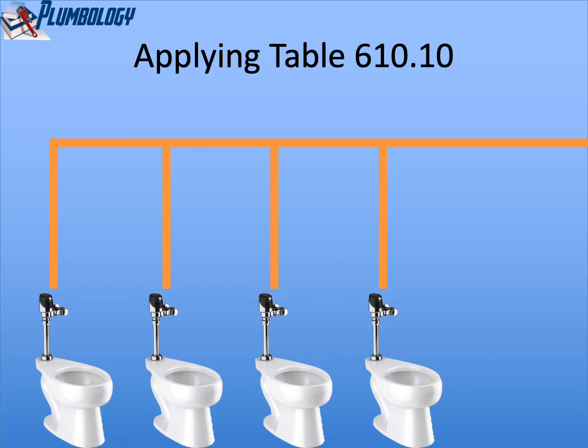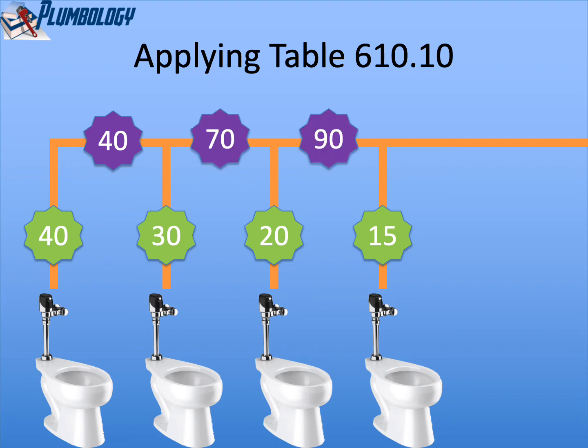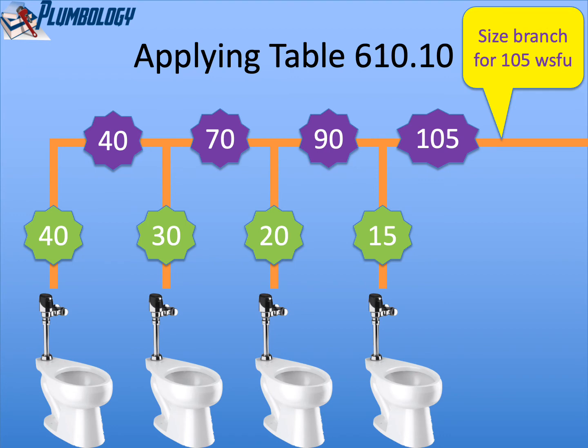Moving on to four water closet flush valves. We use the same decreasing scale: 40, 30, 20, 15. Going back and doing the pipe segments, it'll be 40, 70, 90, and 105. We would size the branch for 105 water supply fixture units.